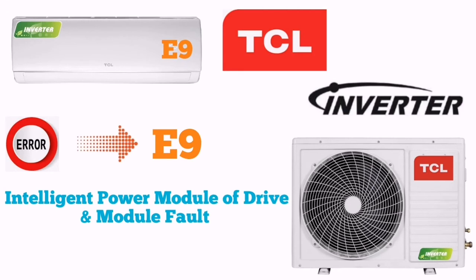When you see error E9 in your outdoor unit, it means intelligent power module of drive and module faulty. It means the module board of our intelligent power module board is faulty. We have to replace the intelligent power module board because it's for power supply and the power supply coming out is not proper, and we have to change it and our unit will be in working condition.